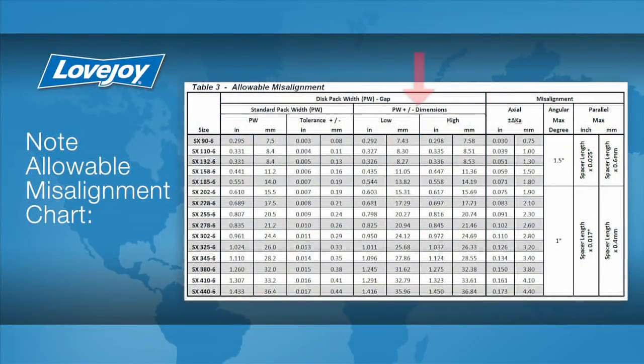All the measurements should fall within the PW high-low range specified in the installation guide. If any of the measurements fall outside the allowable range, you will need to realign the equipment to correct this condition.